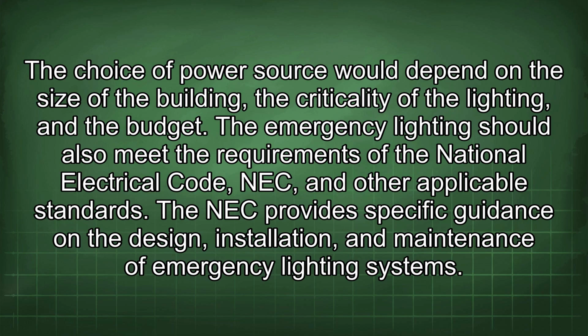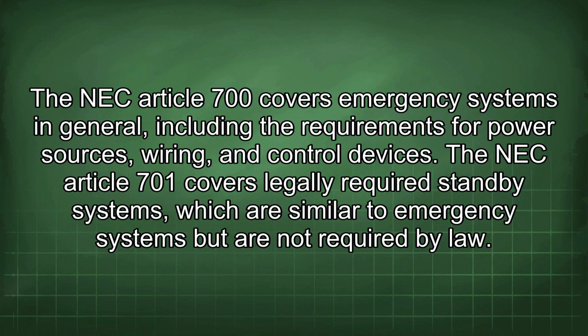The choice of power source would depend on the size of the building, the criticality of the lighting, and the budget. The emergency lighting should also meet the requirements of the National Electrical Code, NEC, and other applicable standards. The NEC provides specific guidance on the design, installation, and maintenance of emergency lighting systems. The NEC Article 700 covers emergency systems in general, including the requirements for power sources, wiring, and control devices.